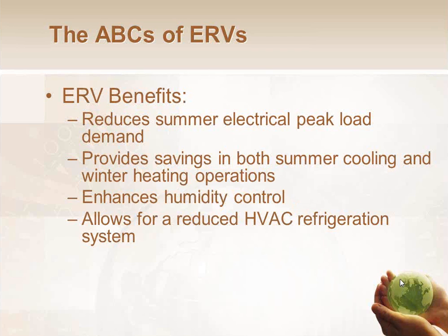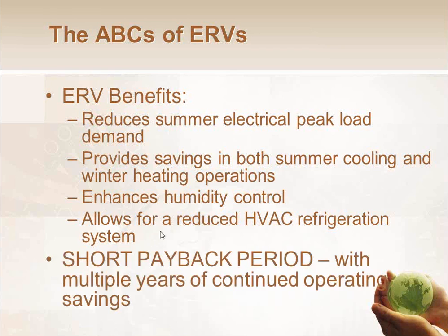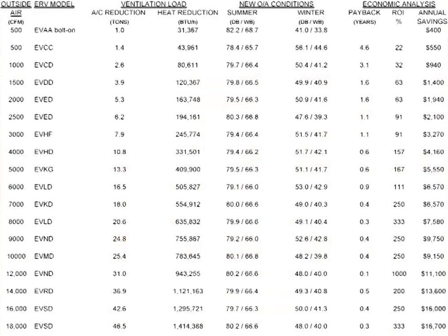Our dehumidification control is going to be significantly enhanced, whether you are in a high humid area or just in a regular Midwestern climate where it's humid only some parts of the year. And the payback on these systems is going to be very large. I'm going to show you some examples here in a minute. But normal paybacks, if you're already replacing HVAC equipment anyway and you're considering adding an ERV, are probably going to be in the 1 to 2 year time frame in most cases. So here's an example of some paybacks that we've calculated. Just a quick background on this particular chart.